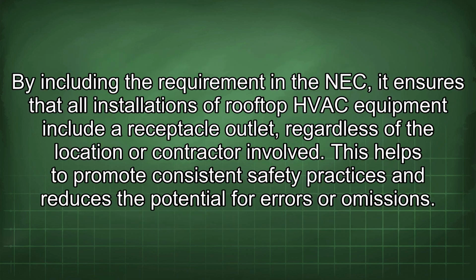By including the requirement in the NEC, it ensures that all installations of rooftop HVAC equipment include a receptacle outlet, regardless of the location or contractor involved. This helps to promote consistent safety practices and reduces the potential for errors or omissions.